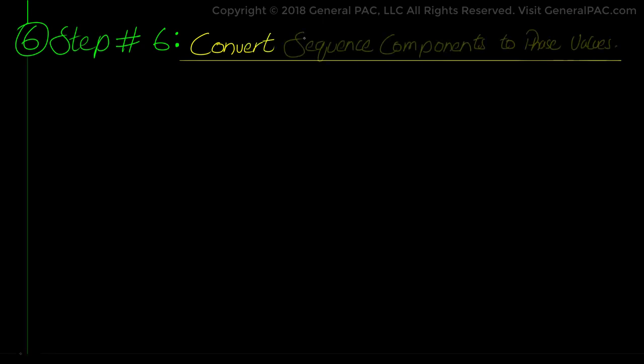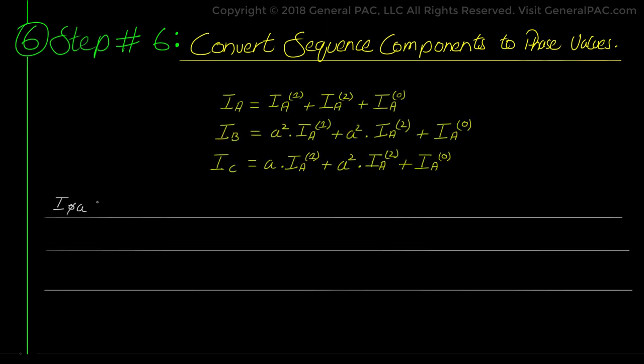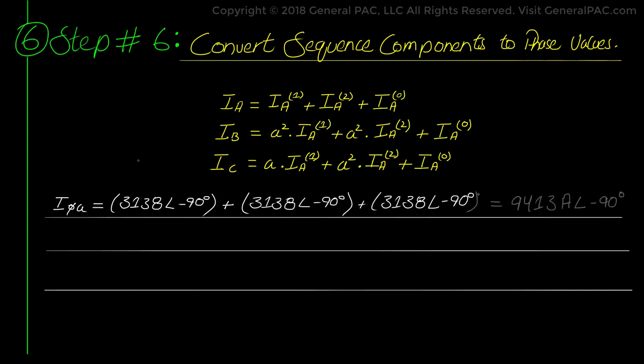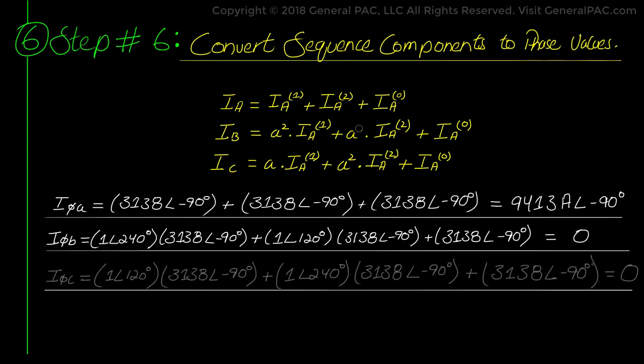As the final step number 6, we convert these sequence component values to phase current values by plugging in the sequence components and the A operators into the familiar equations. For line A current on the 13.8 kV side, we get 9413 amps at the angle of -90 degrees. For phase B line current on the 13.8 kV side, we get 0 amperes. For phase C line current on the 13.8 kV side, we also get 0. This matches exactly what we assumed in our video on single line to ground fault derivations.